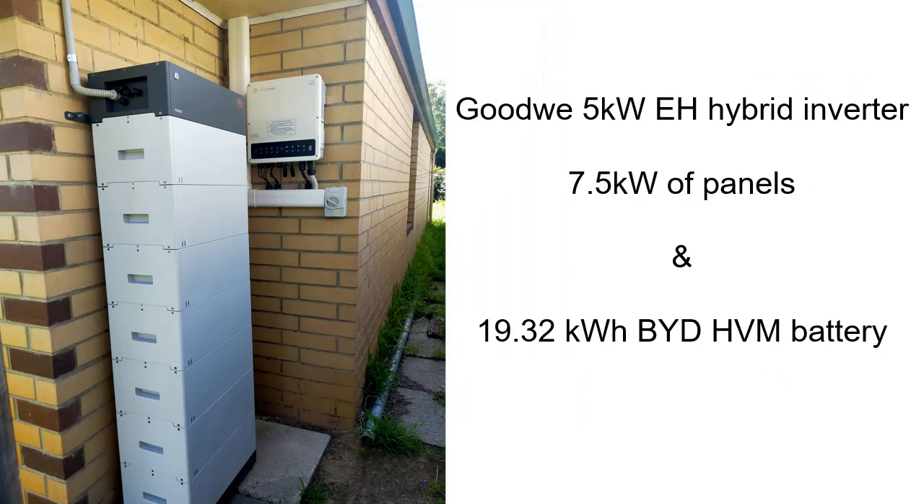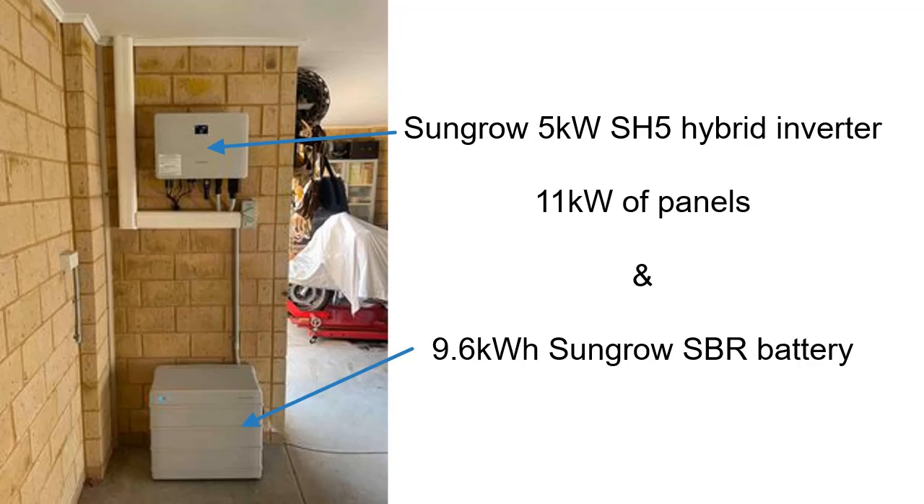This one's a DC-coupled Goodwe EH inverter — 5 kW with 7.5 kW of panels and a relatively large 19.3 kWh BYD battery. And the last recent DC-coupled installation is a SunGrow 5 kW single-phase hybrid with 11 kW of panels — again, oversizing rules apply when you have a battery. It has 9.6 kWh of SunGrow's SBR battery in 3.2 kWh modules, and as you can see from the installation, it could expand up to 20 kWh comfortably underneath the inverter.